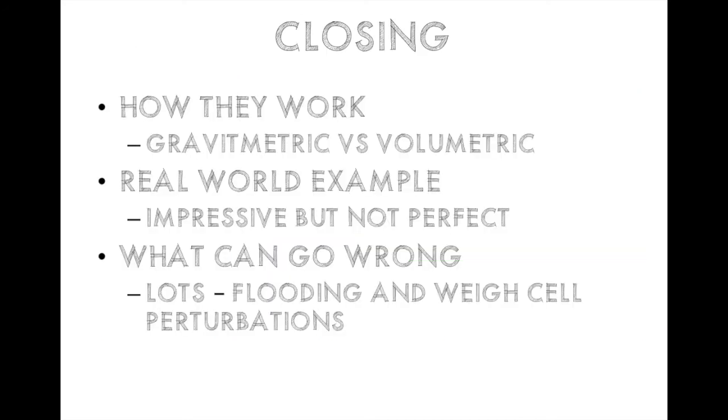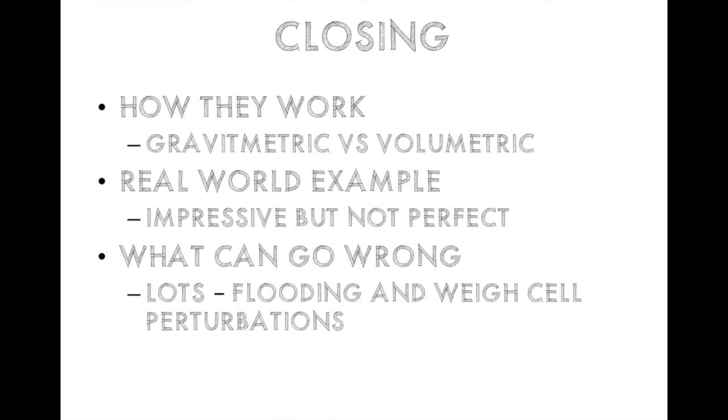So in conclusion, we talked about gravimetric versus volumetric mode. Gravimetric is when it's in steady state. It is relying on its loss in weight data to calculate the flow rate. Volumetric is when it makes certain assumptions while filling in order to depict what the flow rate will be. We showed a real-world example that these pieces of equipment are very impressive, but they're not perfect. And we showed two examples of what can go wrong. Flooding where there's a vacuum pulling powder out of the hopper. And also we talked about weight cell perturbations. There was something making the hopper weight jump, which was causing the K-tron to go into a non-gravimetric mode.